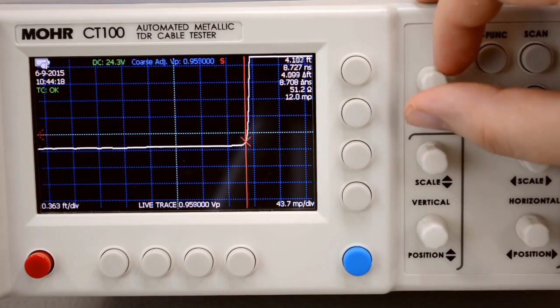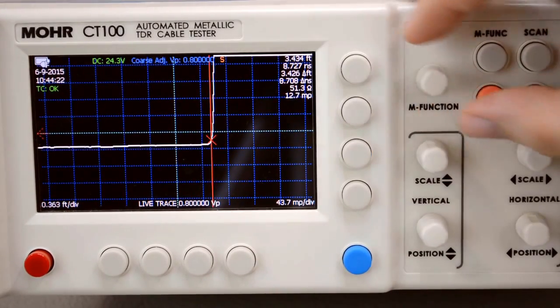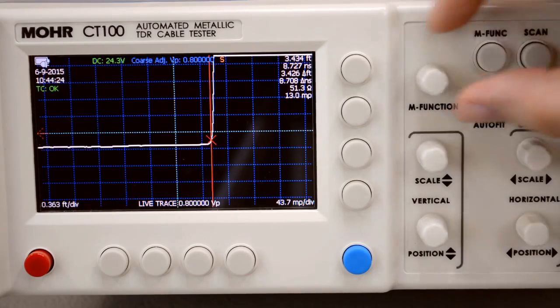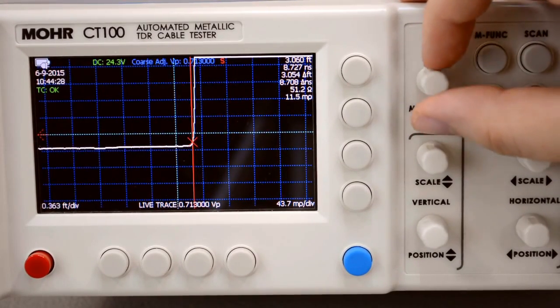So after adjusting the V sub P, just dial it back until this measurement reads the known length of the cable. Since we know the length of the cable is three feet we simply dial it back until we reach three feet. There we go.